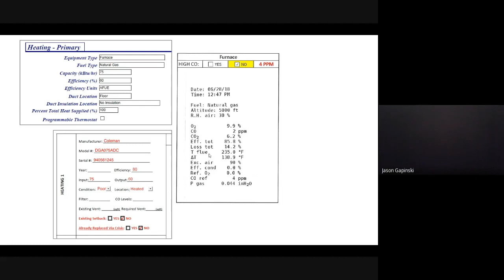This part is the screenshot from the information that was put into the audit, listed at 60% efficiency. This is from the field notes the auditor took, listing the furnace as 80% efficiency. And on the combustion analysis, the measured efficiency was 85. So is this a problem?